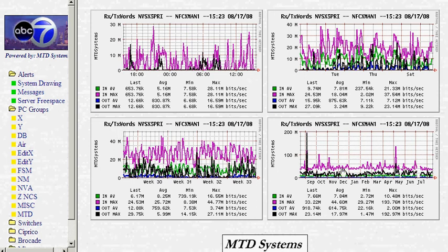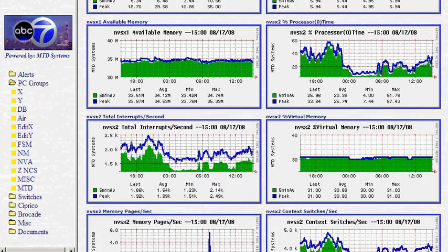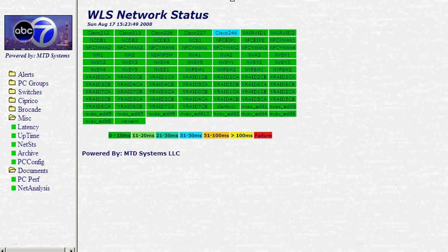Here's another view. This is overall network status, and you can see everybody has a good connection. For some reason, this connection to this particular device was a little slower this time, which may not be a problem. It just may mean a little traffic out on the network. But if a device was constantly one of these higher colors over the course of a year, it might mean that you would want to check that network connection. And again, another drill-in view of one of the processors.